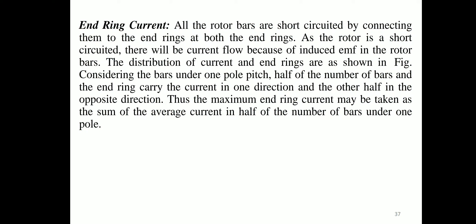All rotor bars are short-circuited by end rings at both ends. Since the rotor is short-circuited, current flows due to induced EMF in the rotor bars. Considering bars under one pole pitch, half the bars carry current in one direction and the other half in the opposite direction. Thus the maximum end ring current is taken as the sum of average currents in half the number of bars under one pole.